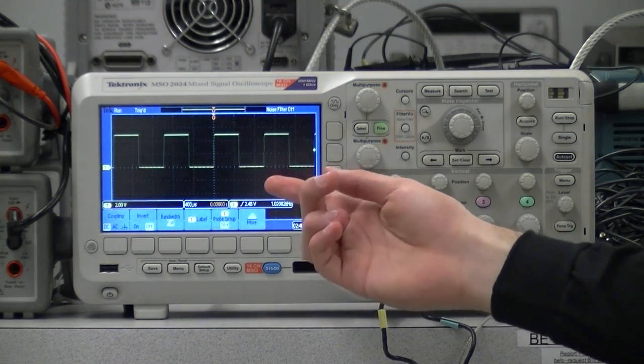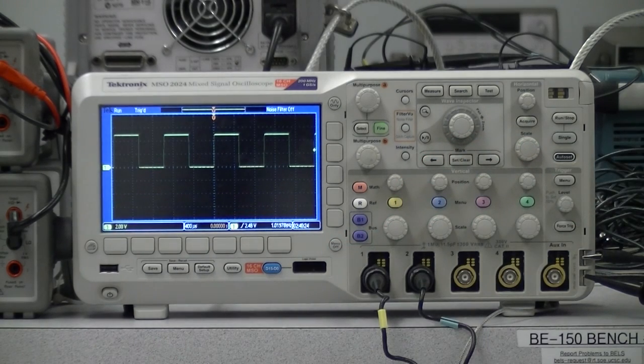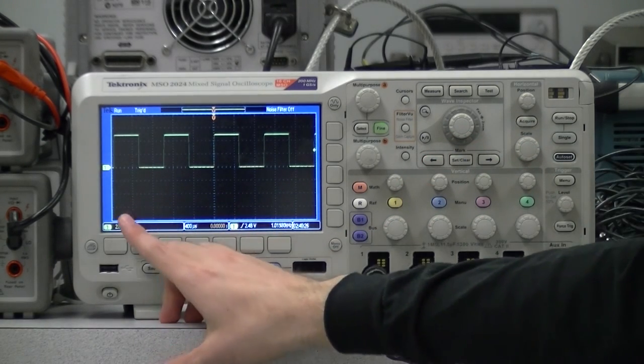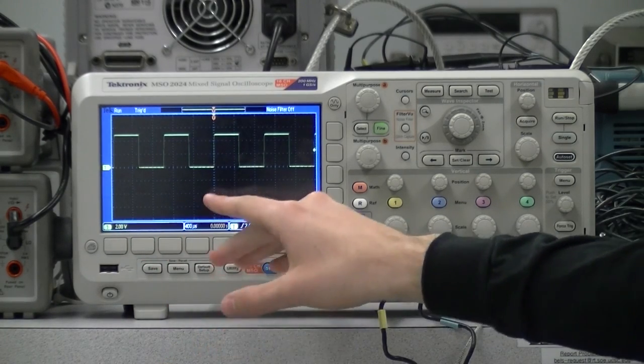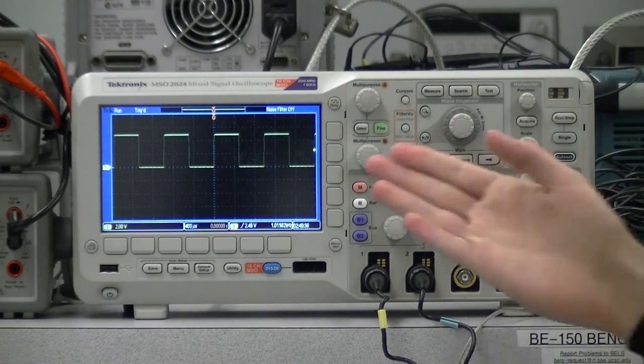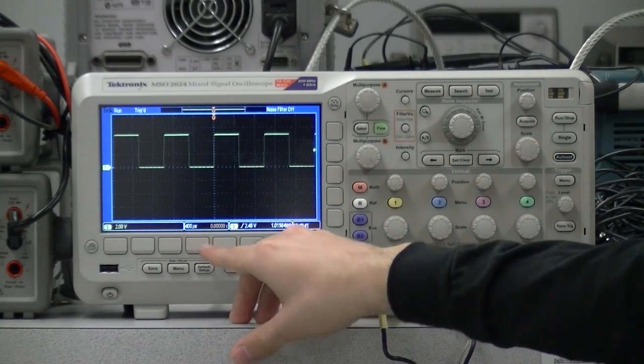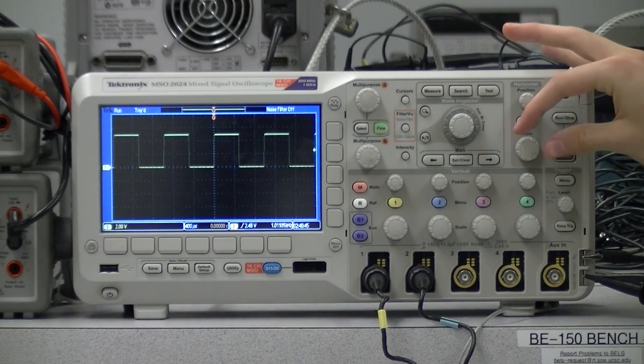We don't always want this menu open, so we can close it by pressing the menu off button here. Now, the voltage per division is still displayed here. The next number that is displayed is the amount of time per division, currently 400 microseconds. This is per horizontal division rather than per vertical division. Since this number will be the same for all channels, unlike possibly the voltage per division, we adjust it with a single knob here.